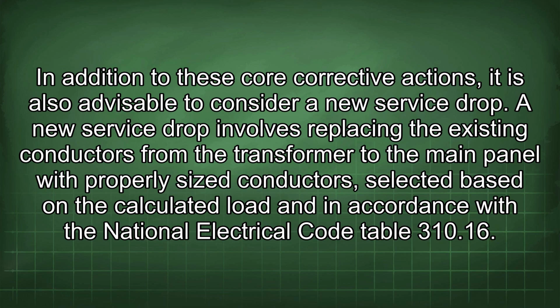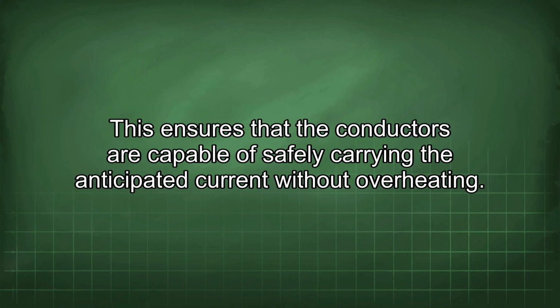In addition to these core corrective actions, it is also advisable to consider a new service drop. A new service drop involves replacing the existing conductors from the transformer to the main panel with properly sized conductors, selected based on the calculated load and in accordance with the National Electrical Code Table 310.16. This ensures that the conductors are capable of safely carrying the anticipated current without overheating.